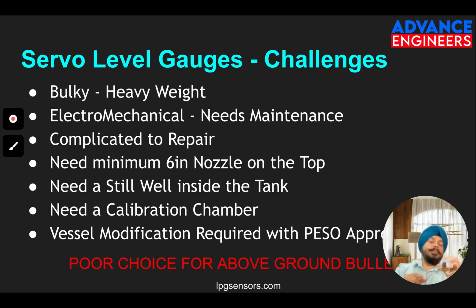There is also a possibility of change in tension because of change in weight of the float itself, or it gets corroded. So there are many things which happen. What you do is you need to have a calibration chamber on top, so you can actually see the movement of the float physically. Once you see that, you can calibrate the electronics. So you need a calibration chamber also.